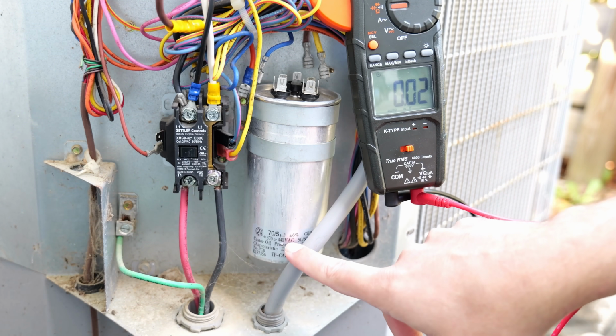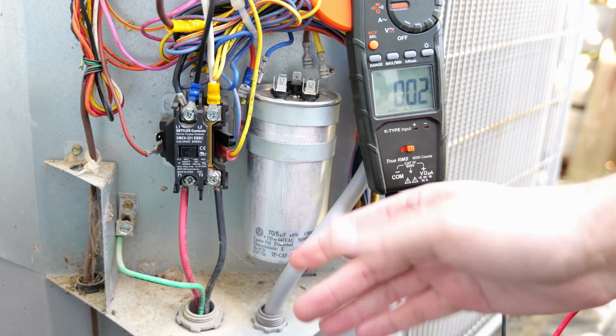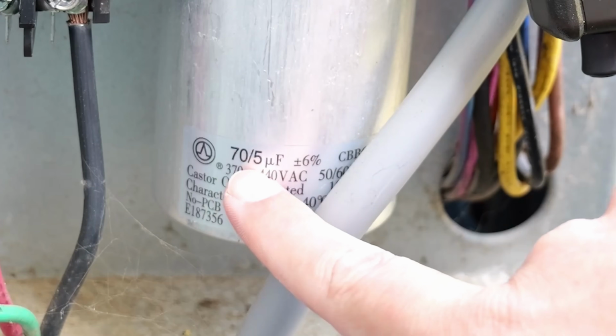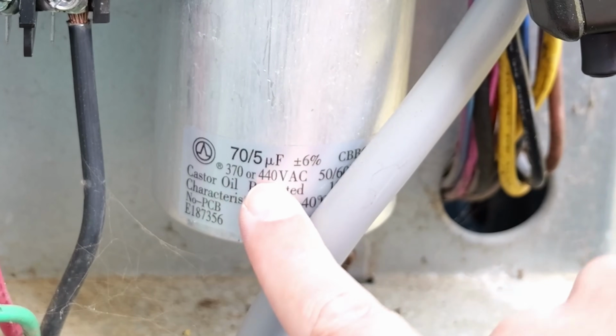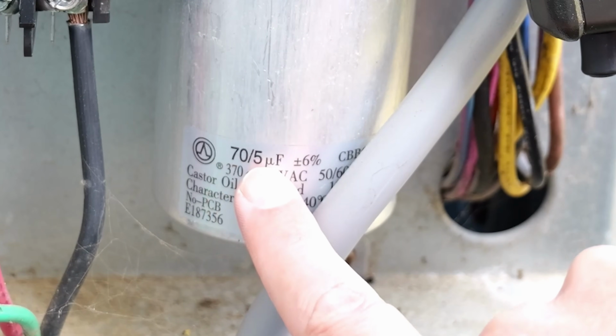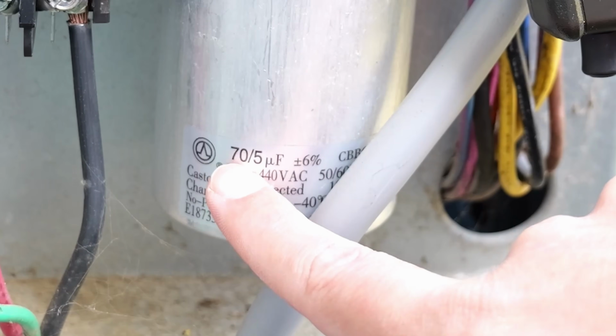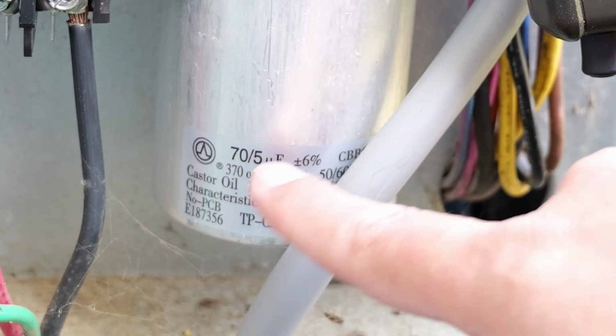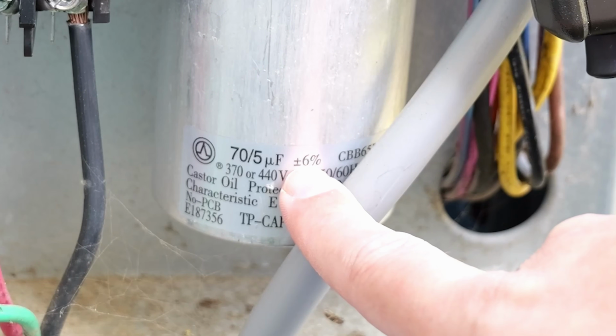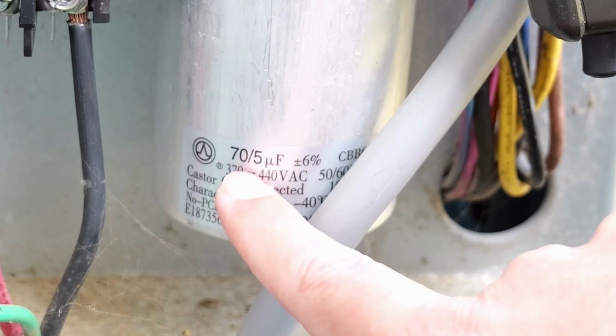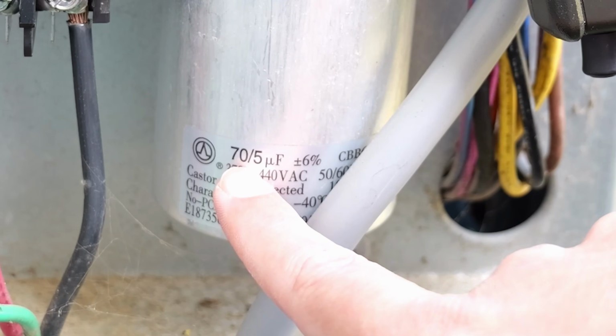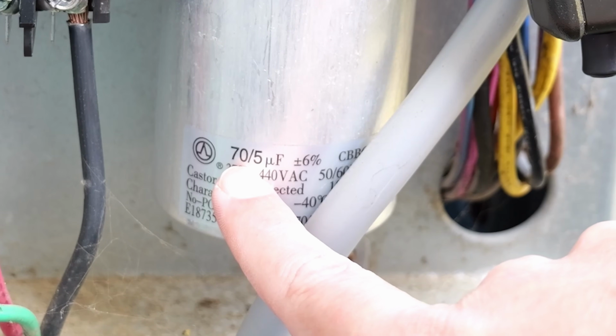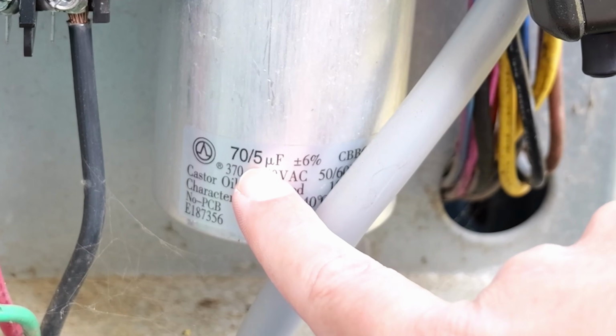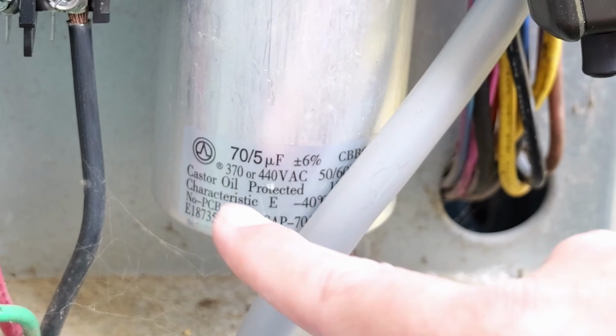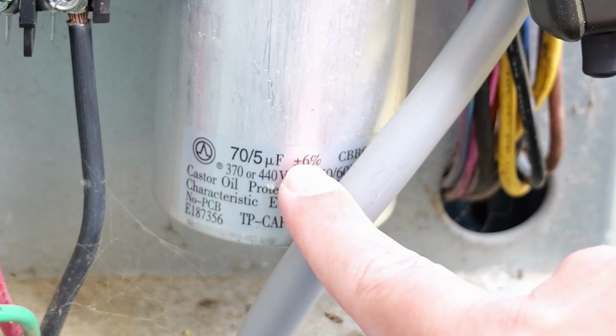One thing to pay really close attention to is, in order to know what your readings should be, there's usually going to be a label on your capacitor which is going to show you what they should be. So on this particular one down here at the bottom, it says 70 and 5 microfarads. The 70 is what we should get as a reading, or over here within 6% plus or minus. So we should get within 6% of 70 microfarads going from the common to the hermetic terminal. The 5 is for the common to the fan terminal. Again, we should get within 6% plus or minus.